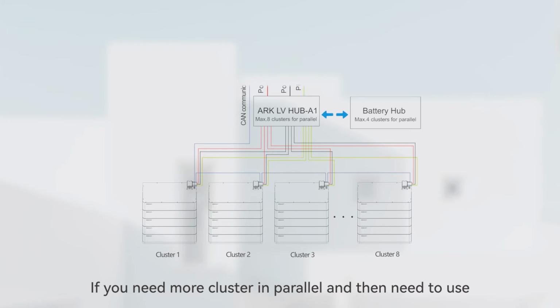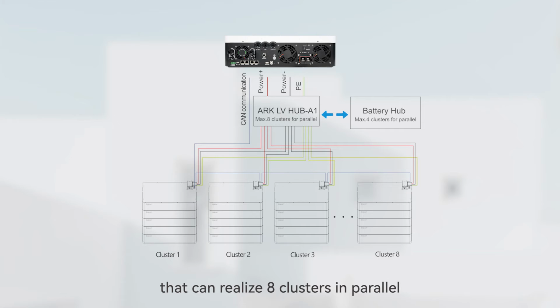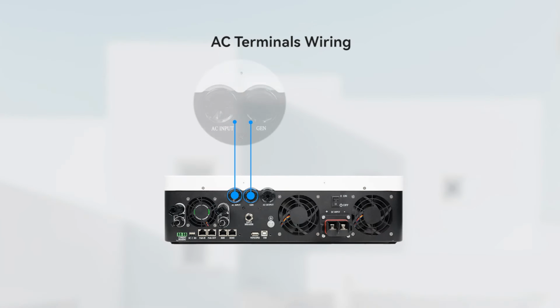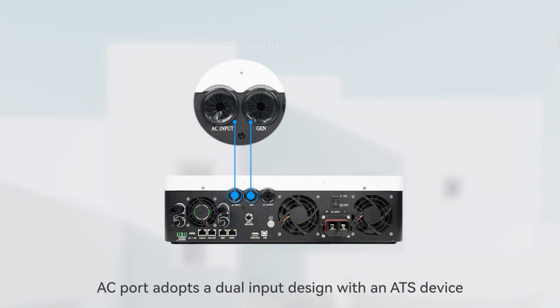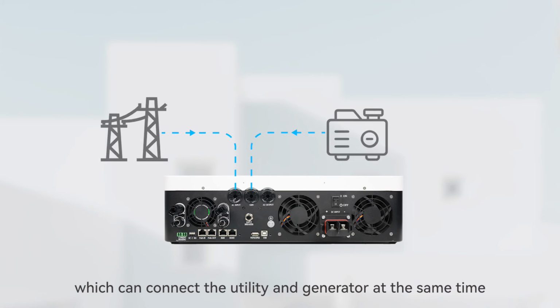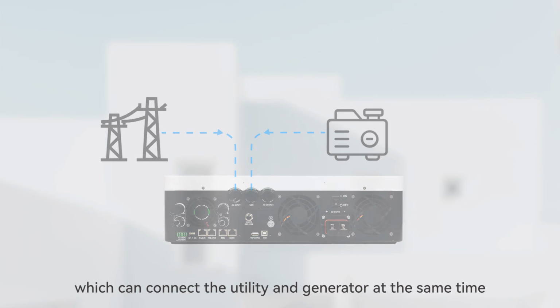If you need more clusters in parallel, then you need to use our battery hub device that can realize 8 clusters in parallel, and system capacity will be up to 400 kWh. AC terminals wiring. The AC port adopts a dual input design with an ATS device, which can connect the utility and generator at the same time.